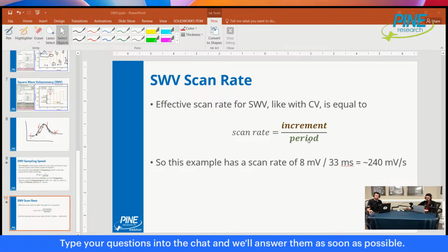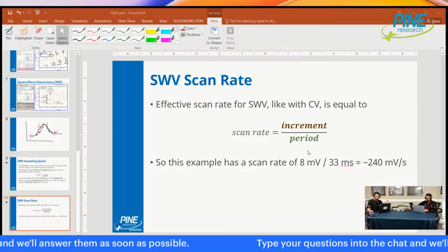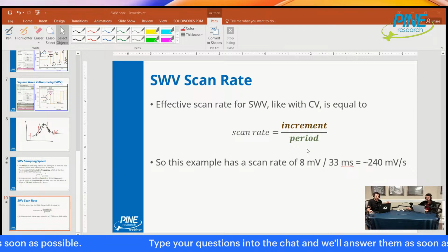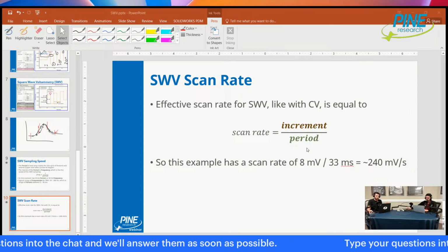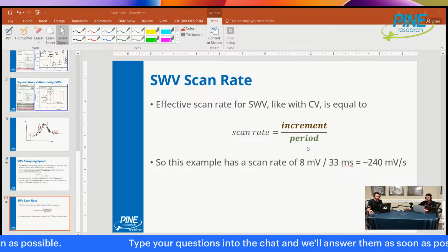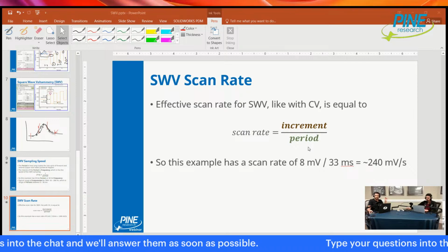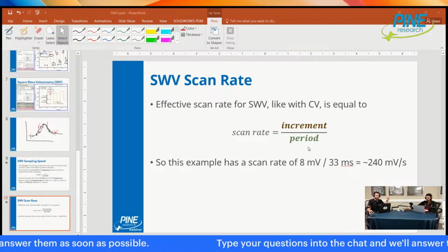Similar to the period, you can decrease the period. But if your period is so short, the measurement might be really noisy because it's up, down, up, down, so fast that the potentiostat can't measure it properly. Beyond a certain point, it's like, can your potentiostat get you a measurement every 100 milliseconds? Fine. Every 30 milliseconds? Probably fine. Every 1 millisecond? Probably. Every 100 microseconds? Well, you're starting to get really fast for the instrument. So at some point, it might not easily be able to measure that. But something in that range, right? Adjusting those parameters with some trial and error.